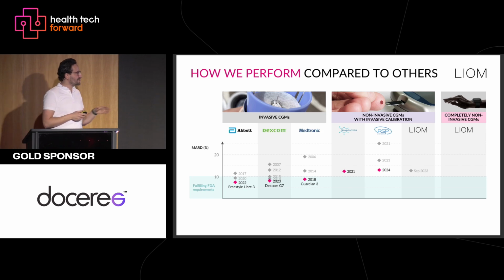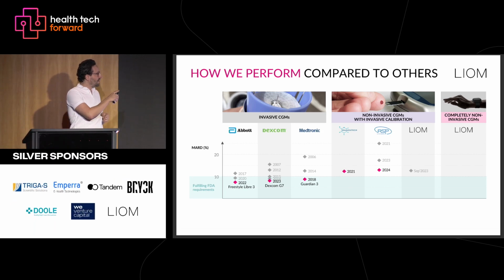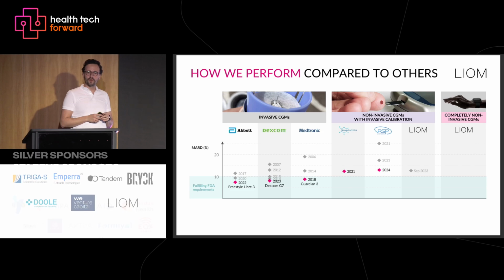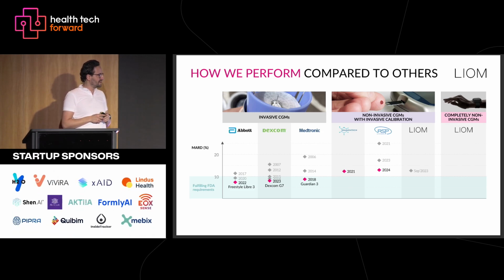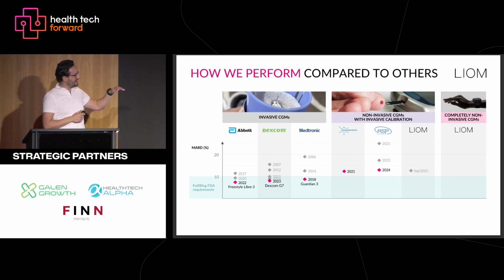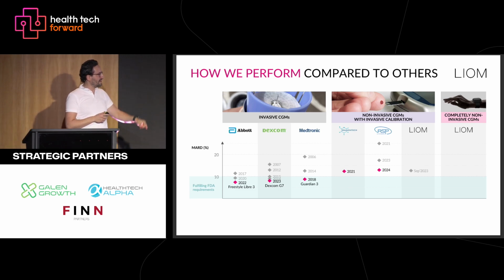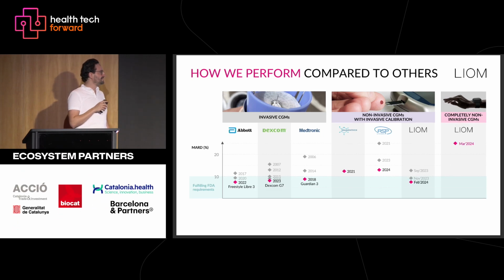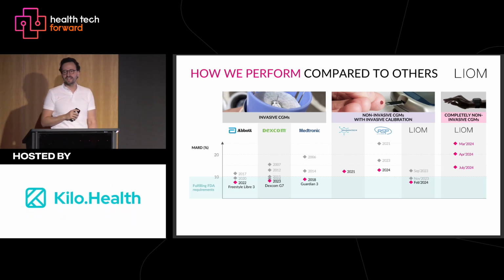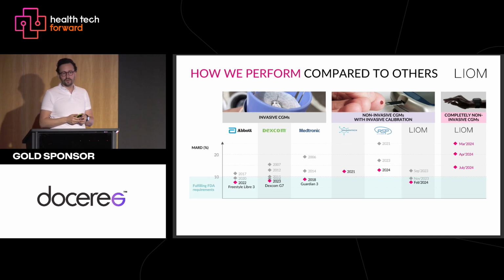And just to give you an idea where this compares in terms of performance, when Abbott and Dexcom, the big duopoly of CGM that cater predominantly to people dosing insulin based on this, launched, they were in their teens in terms of the error to the venous chemical gold standard blood analyzer. Now they are sub 10. We achieved a calibration-requiring MARD in September in the low teens last year, and then in November, sub 10, in February, 7.3, in March we did the first calibration-free 25, then 20.5, then now 14.5. So as you can see, we advanced relatively quickly in improving that MARD. So we not only repeatedly measured glucose non-invasively and calibration-free, we even constantly improved our performance by changing hardware and software at the same time.